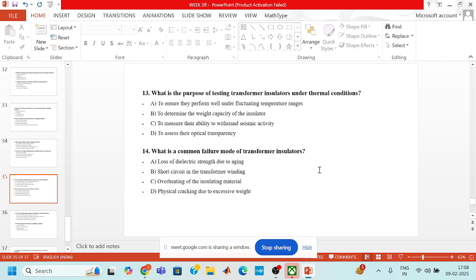Okay. 14th question is, what is the common failure mode of transformer insulators? Option A is loss of dielectric strength due to aging. B is short circuit in the transformer winding. C is overheating of the insulating material. D is physical cracking due to excessive weight. A. 14th. Loss of dielectric strength due to aging.